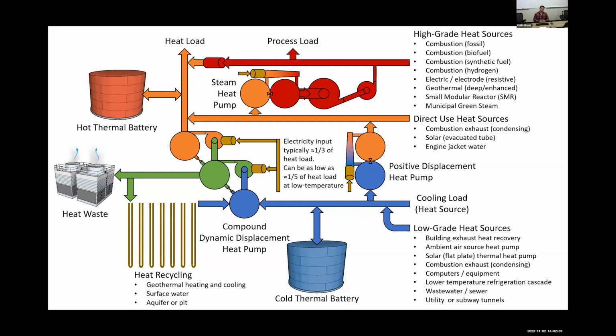But there's only so much chilled water demand on campuses during colder weather. And so you get to the point where you've made all the chilled water with your heat recovery chiller, but you have not made all the heating that you need for the system. So this diagram here, which would require a lot more time to explain in detail, basically shows how you can move different heat sources around, and particularly in the bottom right corner, there's a number of other low-grade heat sources that are available on many campuses that can be connected on to a chilled water system.